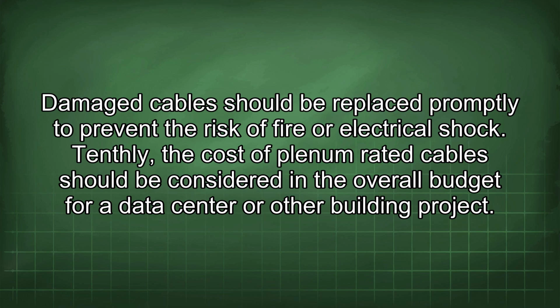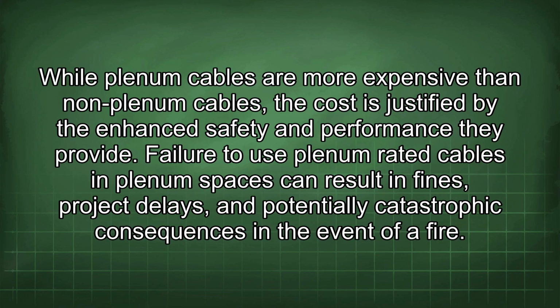Tenthly, the cost of plenum-rated cable should be considered in the overall budget for a data center or other building project. While plenum cables are more expensive than non-plenum cables, the cost is justified by the enhanced safety and performance they provide. Failure to use plenum-rated cables in plenum spaces can result in fines, project delays, and potentially catastrophic consequences in the event of a fire.